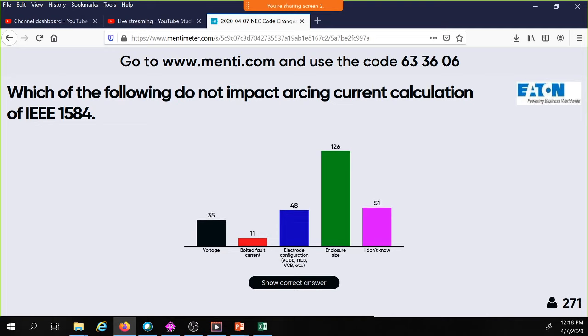So when I have a very large enclosure, I will have that energy come out at a certain rate. But when I constrict that arc, I will cause that energy to come out forcefully and reach a further distance, because I have reduced the enclosure size. But I haven't changed the electrode configuration. I haven't changed the distance between the electrodes. I haven't changed the voltage. I haven't changed the bolted fault current value. So I won't change the arcing current, but I will change the amount of force that the electrical worker faces in front of that enclosure. So the right answer to this one that doesn't impact arcing current is the enclosure size. All of those other parameters besides the I don't knows do impact arcing current.